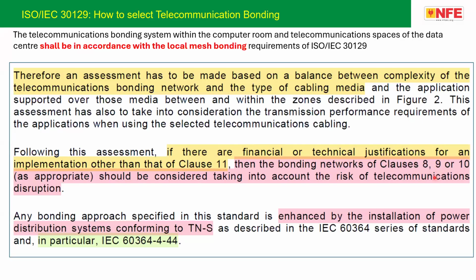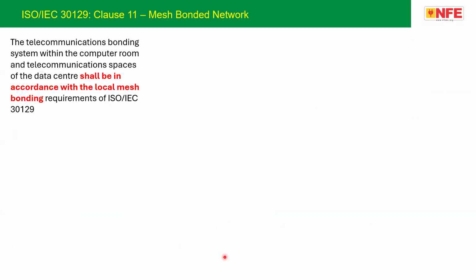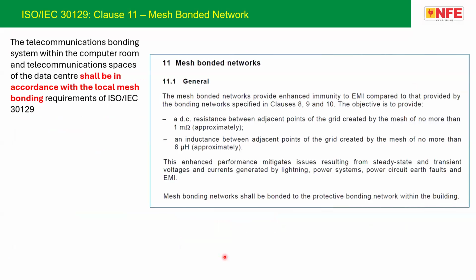I'm showing you 9 and 10 later. The assessment also says any bonding approach specified in the standard is enhanced by the installation of a power distribution system conforming to TNS. So TNS system is like a mandatory requirement, in particular 60364-444. So it's very interesting to find out what exactly these standards are saying.